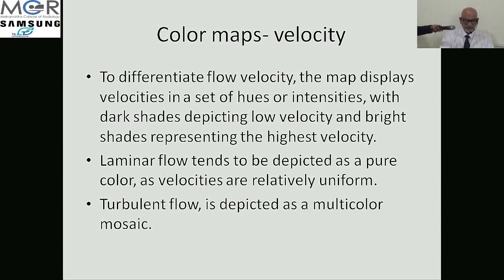Now here are color map velocities. Another thing: I have told you about the color code, blue and red. Now the color map differentiates flow velocities. Although the flow is going towards the probe, it will be red, but flow velocities again have different shades of red. So the map displays velocity in different hues or intensities, with dark shades depicting low velocity and bright shades representing higher velocities. So dark red means low velocities, bright red means higher velocities going towards the probe. Laminar flow tends to be depicted as pure color. If there are multiple frequencies, then you have multiple shades of red or blue. But if the flow is laminar without turbulence, then the velocities will be pure color.